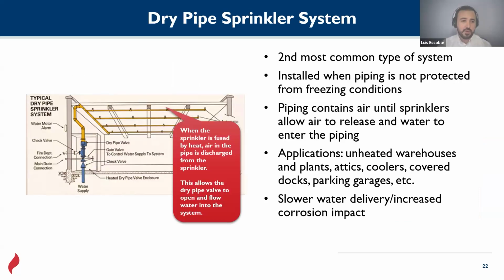The second type of fire sprinkler system is a dry pipe sprinkler system. In this case, I'm going to go to the image. We see the blue part of the system. This part always contains water. But the yellow pipe is all dry. That's why we call it dry. There's no water inside it. It's a closed system. Most of the time we fill these pipes with air or nitrogen. It could be either of them.